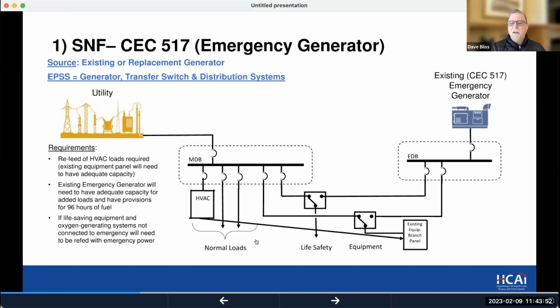Finally, you'd need a means to store fuel. The 96-hour fuel requirement has some nuances: you can have 6-hour on-site storage plus 90 hours of available energy or fuel resource delivered to the site, whether that's additional diesel fuel, electrical energy, gas, or another resource. The state will likely be relatively agnostic as long as it meets safety requirements.